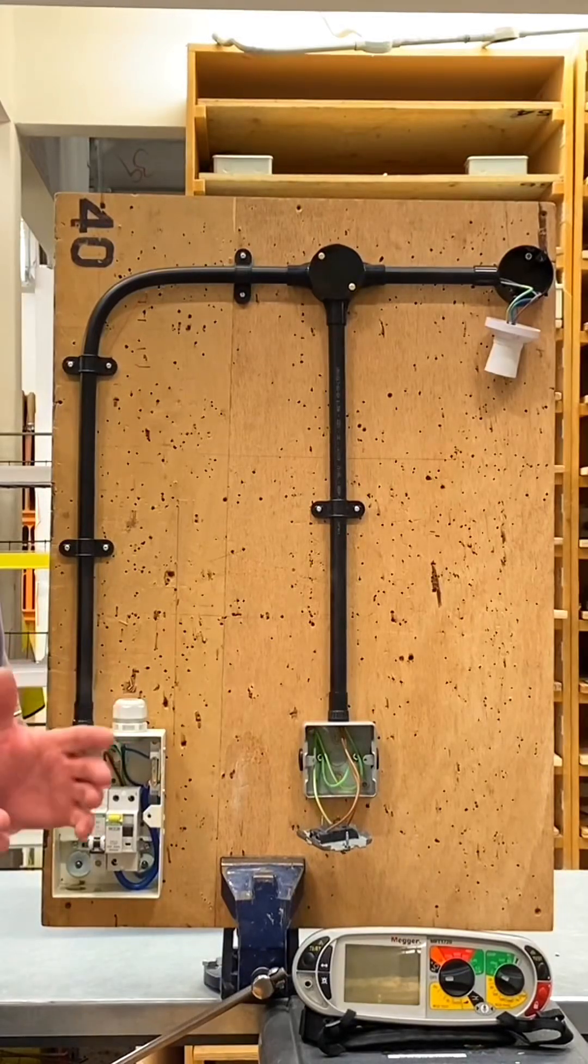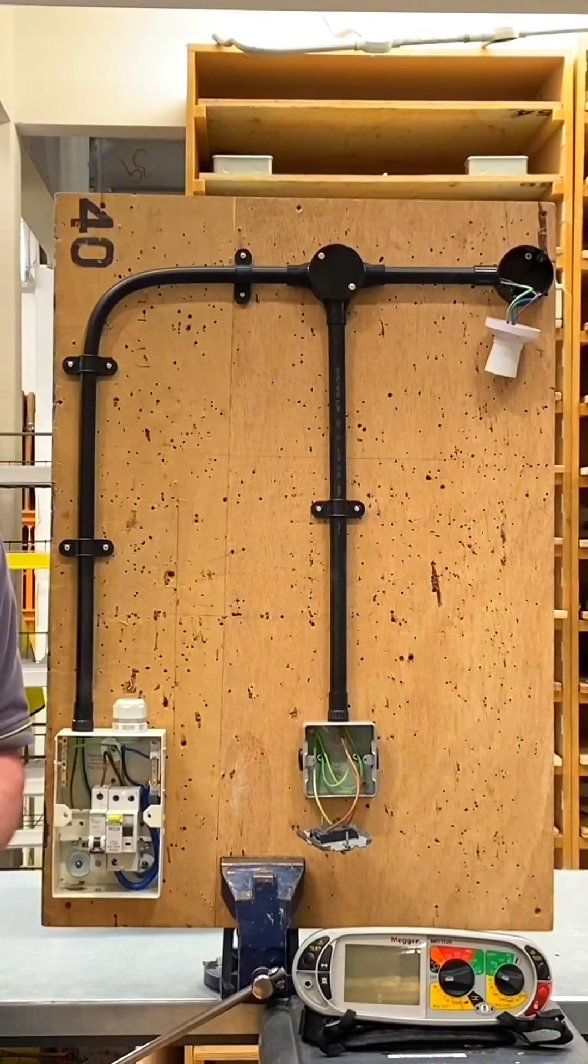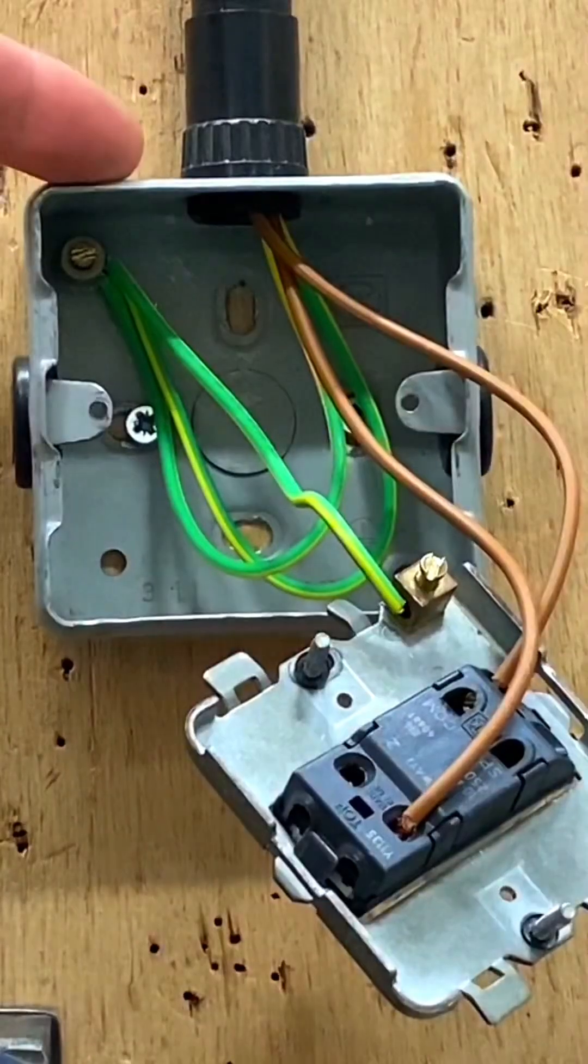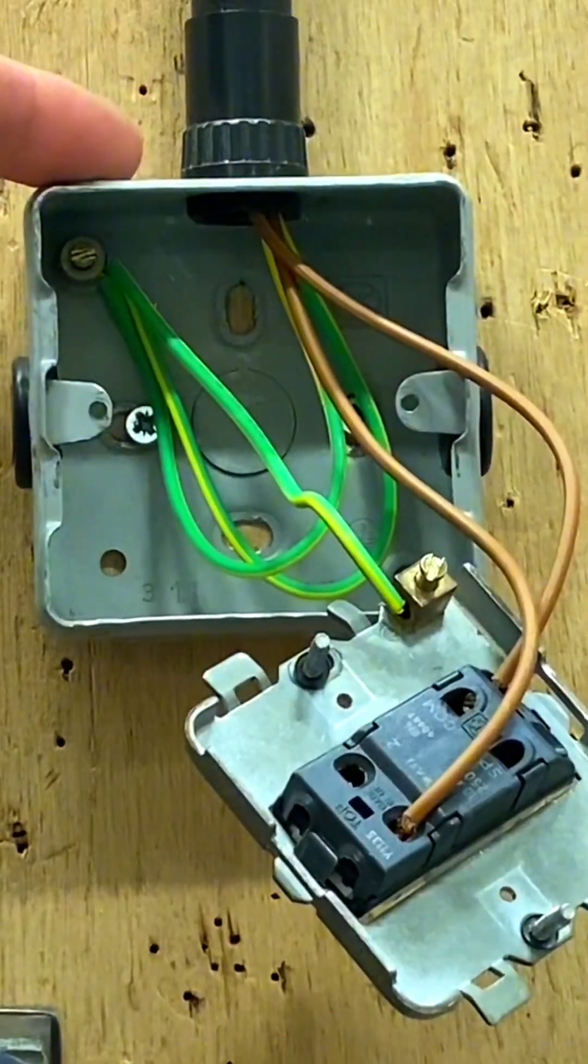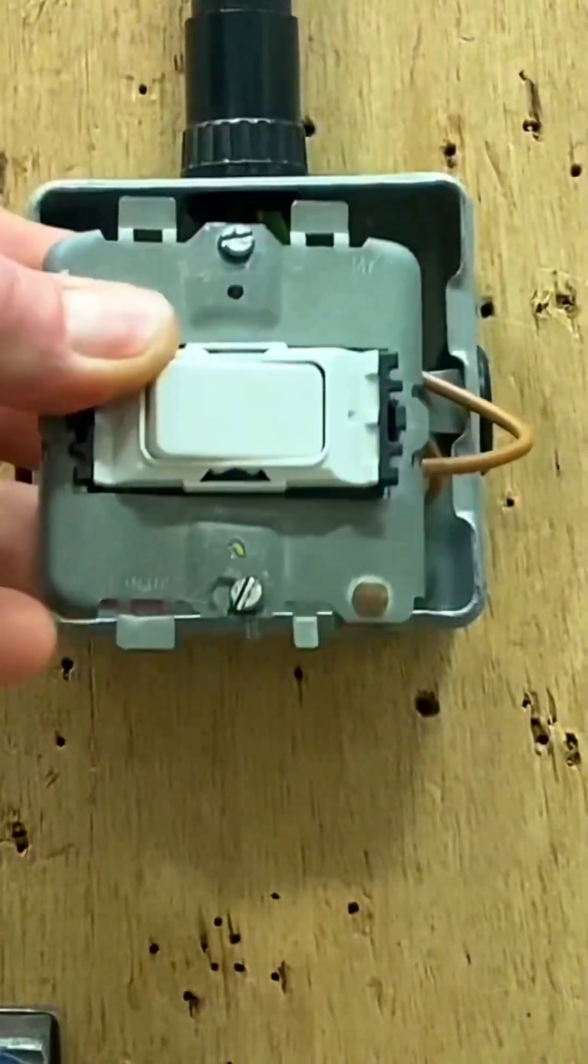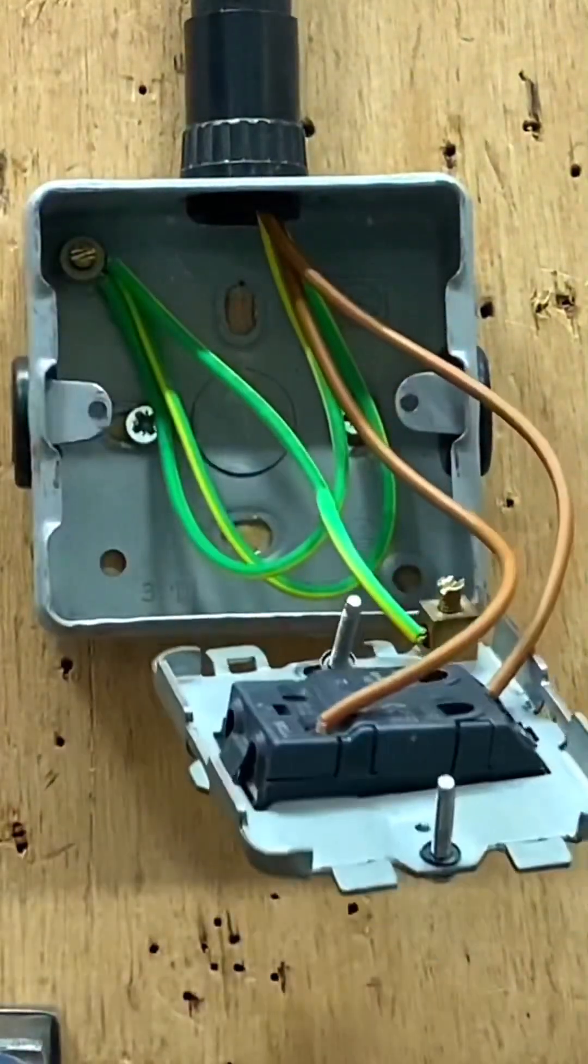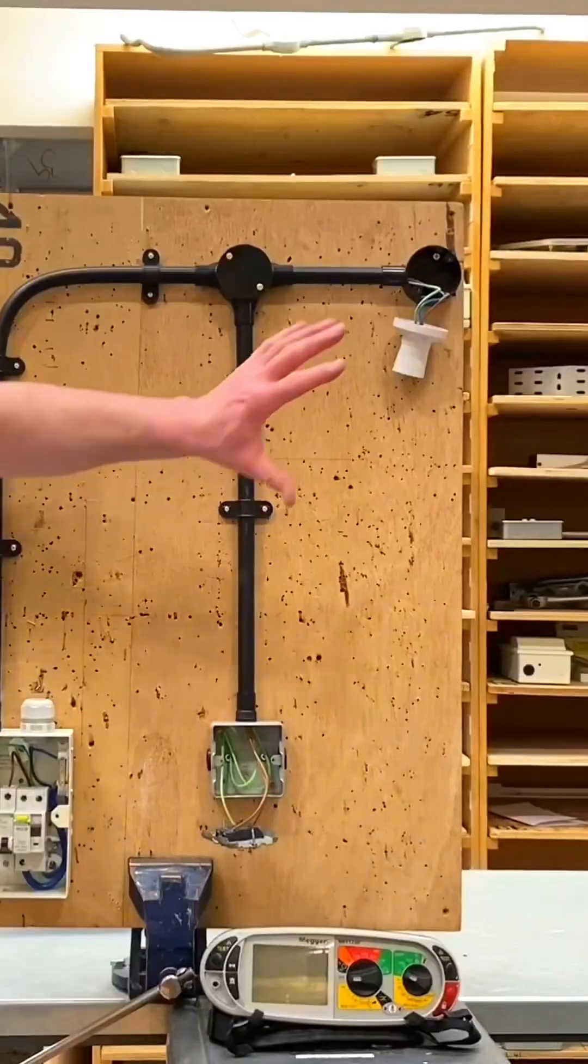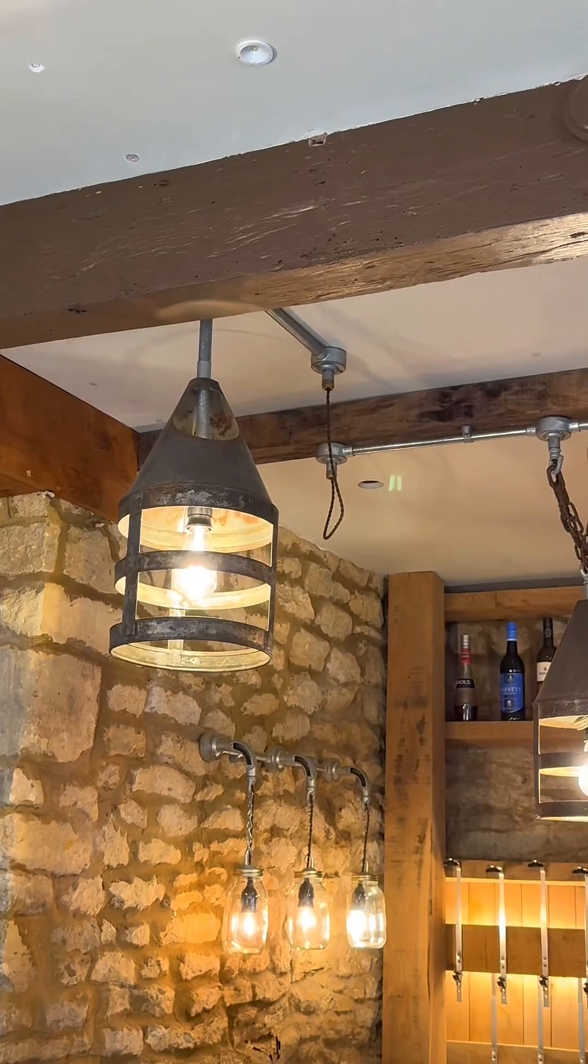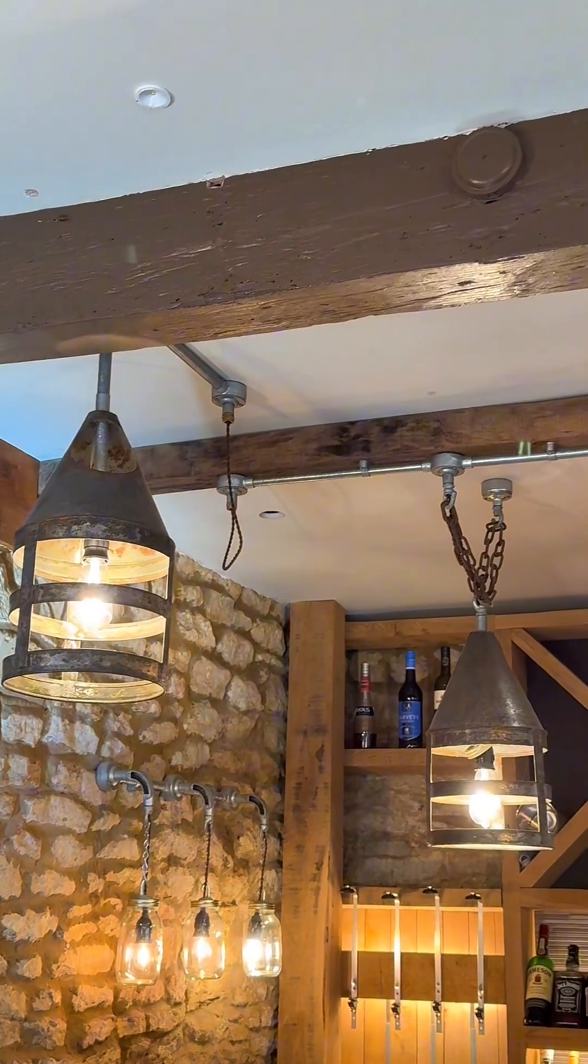We're going to look at the continuity of CPC, polarity, and insulation resistance tests. It's really important that we prove the CPC gets to the exposed conductive part of the box, the frame that holds the switch, the CPC connections within the accessory, and up to the plastic light fitting in case it's changed to a metallic one in the future.